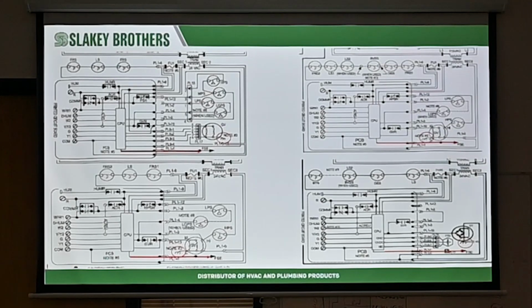It should just have a terminal, a green wire on the sheet metal. Which unit are you referring to? Which model? All of the units, like a regular one. So high efficiency has 3 wires, but the simple units, oh, you mean like an 80% furnace? Yeah. I'll look at that here in a second, but I'm pretty sure they all need a good ground, or they will not work. No, they just have a terminal, not the wire. What do you mean? I mean, just a terminal on the metal plate of the unit. Yeah, and they don't have a green wire. Oh, so I see what you're saying.